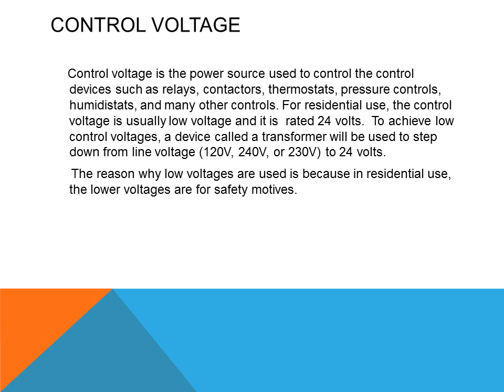Control voltage is the power source used to control devices such as relays, contactors, thermostats, pressure controls, humidistats, and many other controls. For residential use, the control voltage is usually low voltage rated at 24 volts. To achieve low voltage controls, a transformer is used to step down from line voltage — usually around 120, sometimes 240 or 230 volts — down to 24 volts.